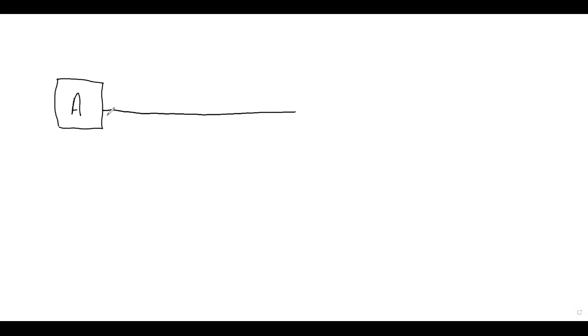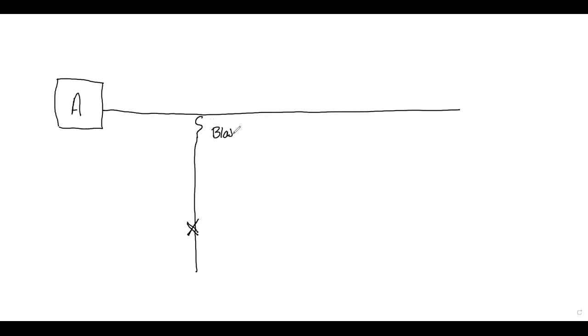On the whiteboard: I've got a breaker in a substation — I'll call this Breaker A — then going out on the feeder circuit. The one you're most familiar with right now is of course a fuse. Let's say a bird flies into the line and gets into two phases at one time, causing a fault. What do we want the fuse to do? Blow. There's no technology inside a fuse — it's just going to blow if we have a fault.